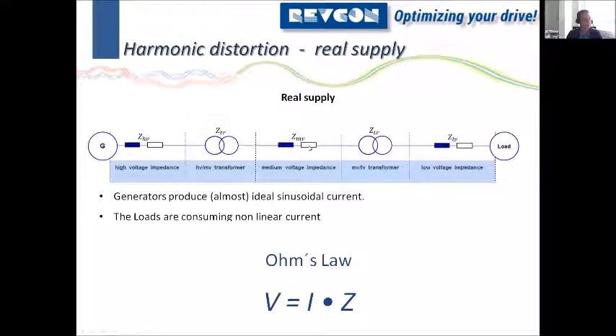So basically, when we look at Ohm's law, we can say if we have a current and we have an impedance in the system, this can be the wires, this can be the transformer, and especially in South American countries, from as far as I am aware, you will also have quite long medium voltage impedance, meaning long distances of medium voltage. Based on that, you will see distortion also made by this impedance. So, long story short, every current will cause a voltage distortion. If I have a current on the 250 hertz signal, and I have an impedance which is also defined for 250 hertz, then I get a voltage distortion on the fifth harmonic. That's how simple it is.